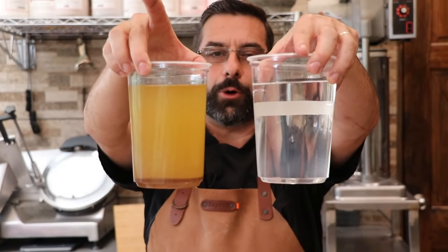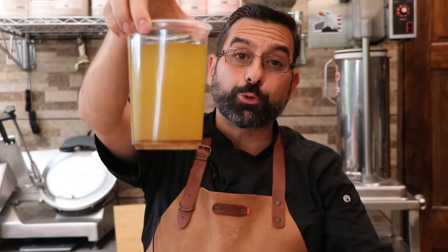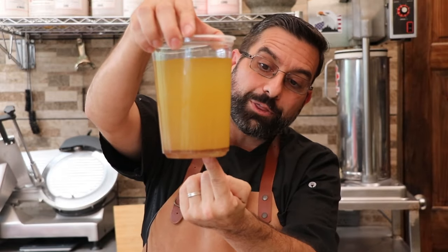This is what it's supposed to look like before it goes in. So we've got super dirty oil with water inside the oil. And that let me know that there may be a problem with the demister. Maybe it's full of oil. Maybe it's full of gunk or clogged up and it wasn't doing its job. And that's what led me to take it apart and clean it. So let me show you how we did it.